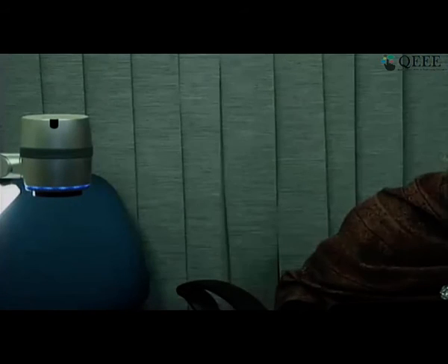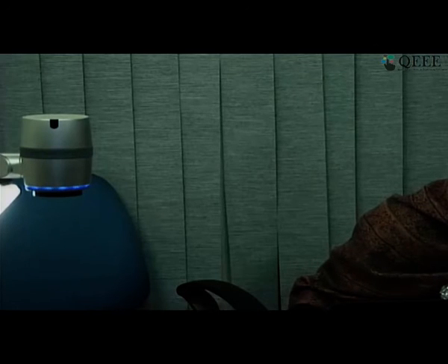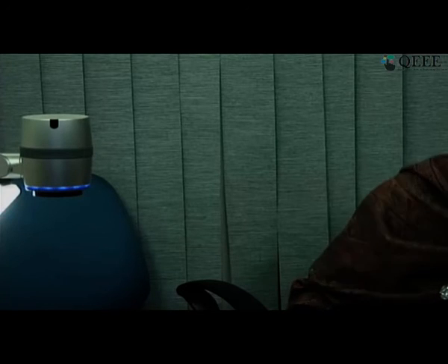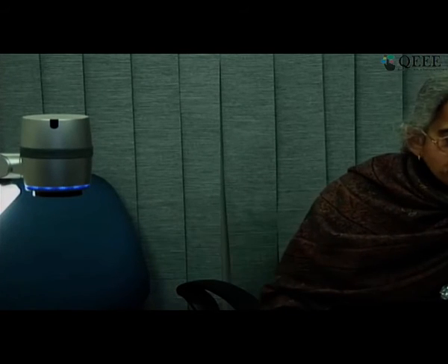Okay. Another question is, what is the conductor size in the primary of a power transformer for high currents? See, it depends absolutely upon the rating that you are talking about, because a power transformer can be of various ratings. For example, if you look at Ramagundam power station, many of them are 500 MVA generators. So the corresponding transformers are to be of 500 MVA rating. For 500 MVA, you can calculate the current. Let's calculate.